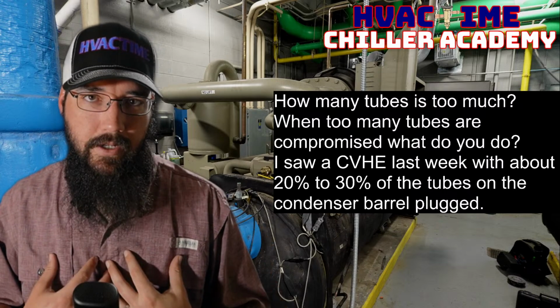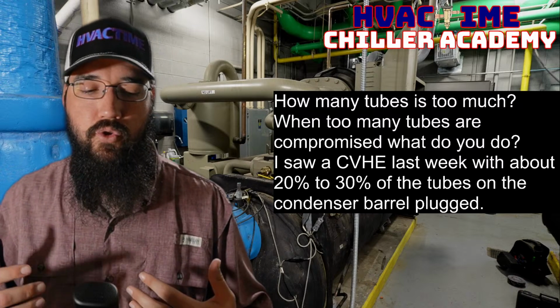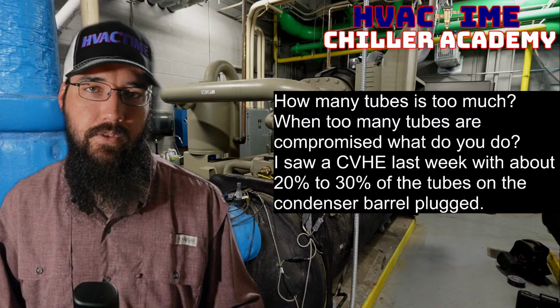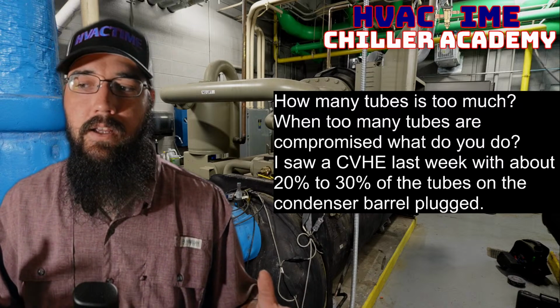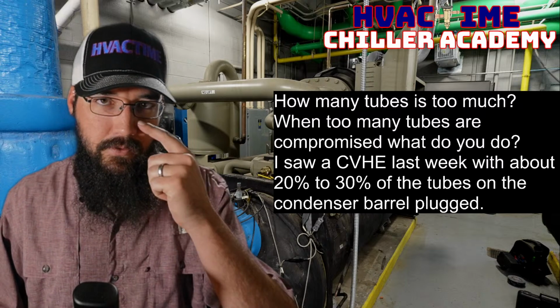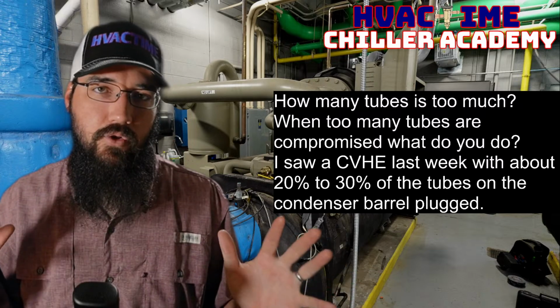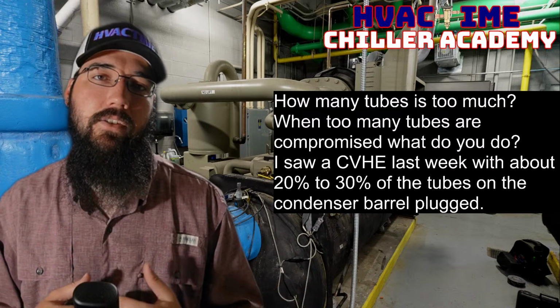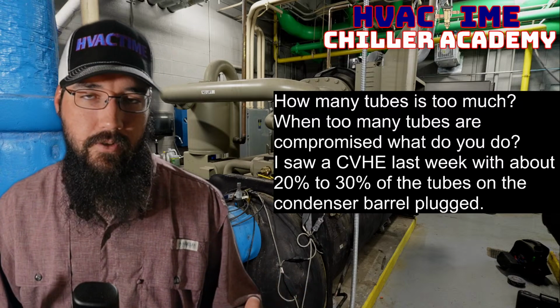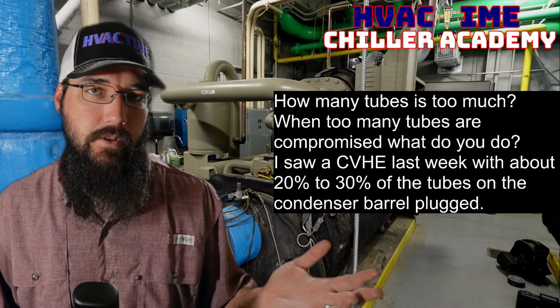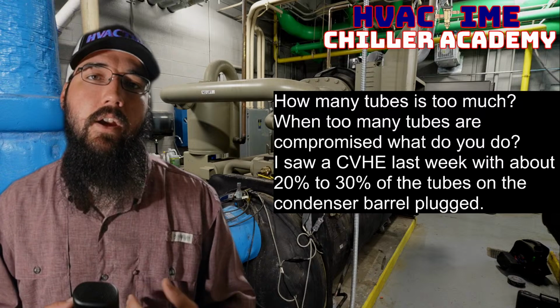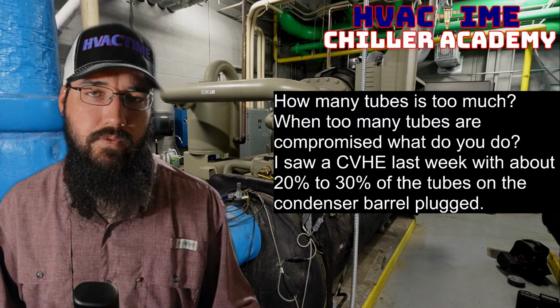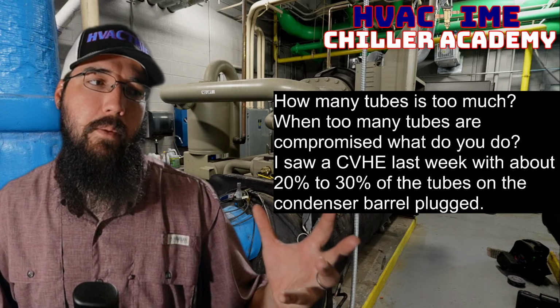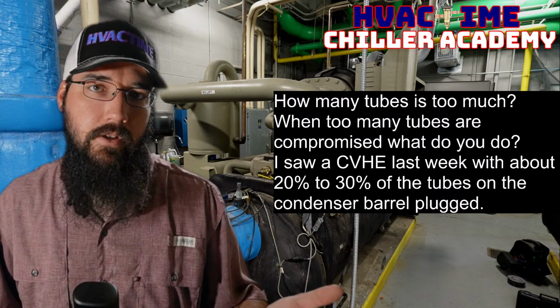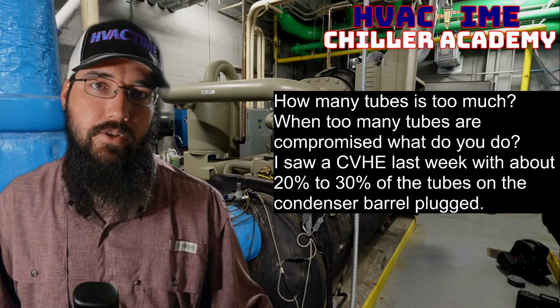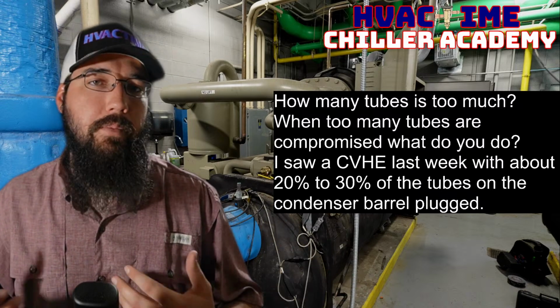My personal training that I've come up understanding is usually somewhere about 15-20%, maybe even as low as 10% on some machines. Just kind of depends on your circumstances, but somewhere in that range, you will start to see pretty significant heat exchange degradation. Now, if that means it's on your evaporator side and you've had to plug a bunch of tubes there, well, then you're going to be running much higher approach values. You're going to be struggling to make leaving water set point without pushing your evaporator saturation down too far. So that would be a symptom, right?